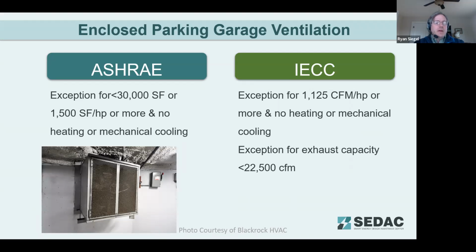So also for ventilation, ASHRAE does have an exception for smaller square feet or ventilation that has high performance or high efficiency. So it's able to cover up to over 1,500 square foot per horsepower, and with no mechanical heating or cooling, then you don't have to do the demand controlled ventilation. Whereas IECC sets that target at least 1,125 CFM per horsepower. So the ASHRAE standard is a little bit more strict at 1,500 CFM per horsepower.